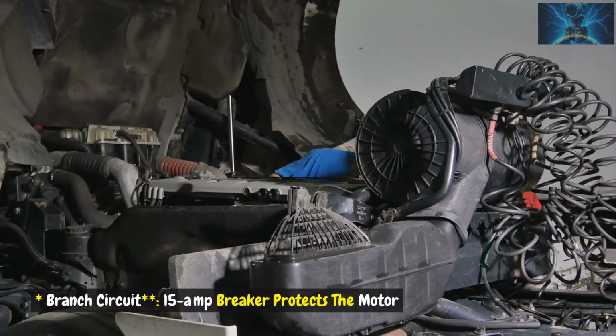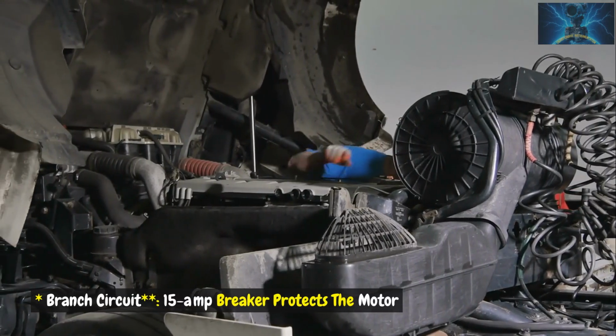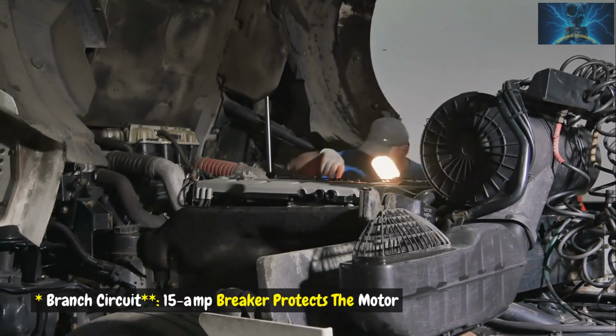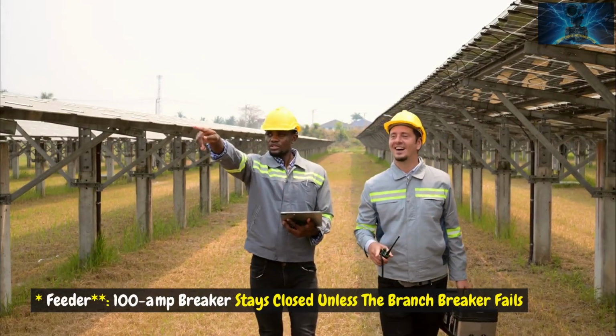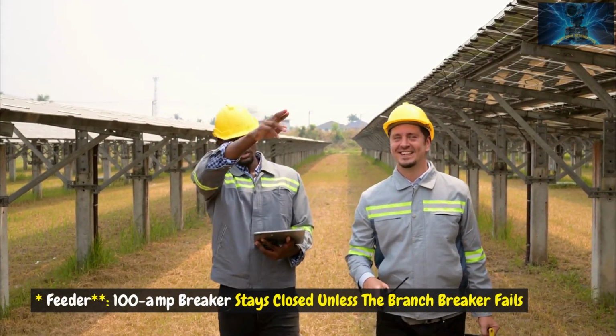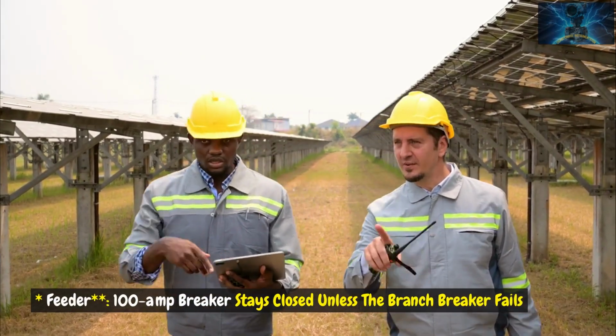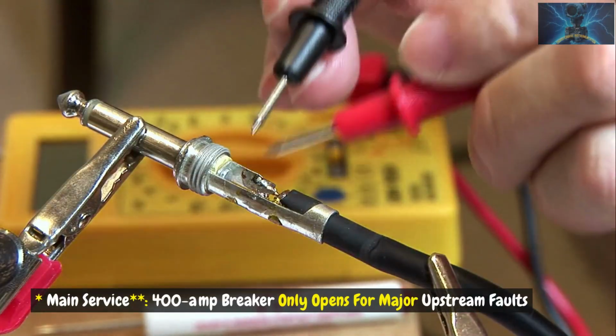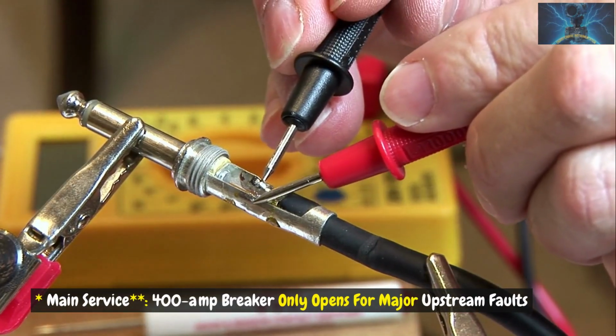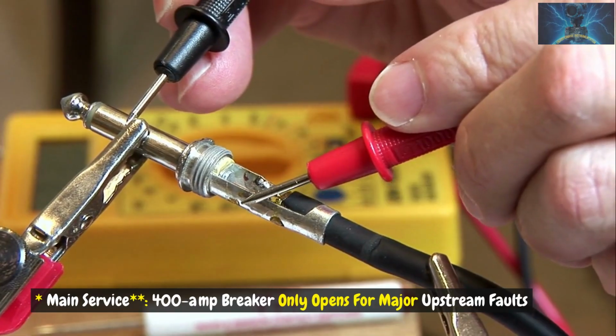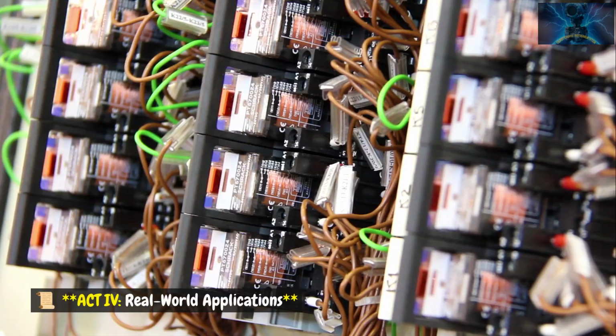Example: branch circuit. A 15 amp breaker protects the motor feeder. A 100 amp breaker stays closed unless the branch breaker fails. Main service. A 400 amp breaker only opens for major upstream faults.